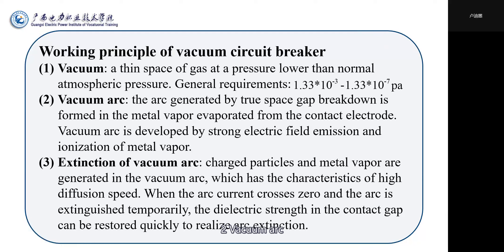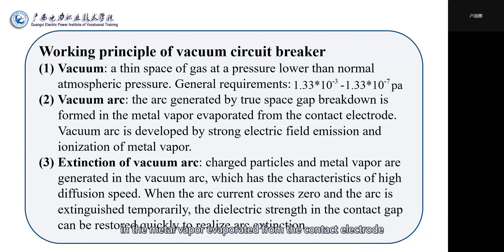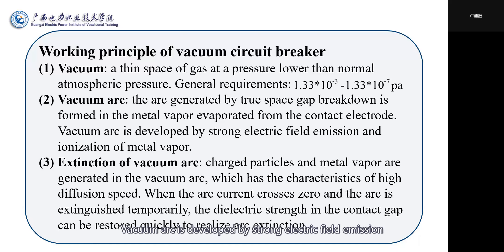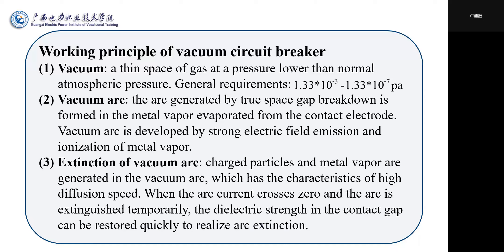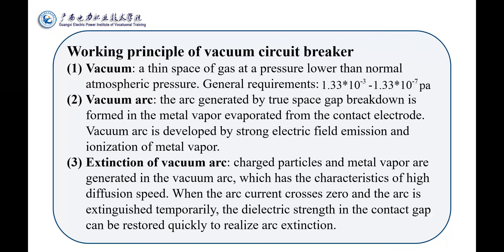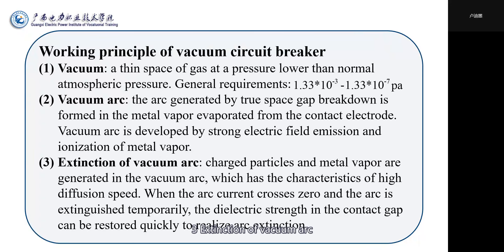(2) Vacuum arc: the arc generated by a vacuum space gap breakdown is formed in the metal vapor evaporated from the contact electrode. Vacuum arc is developed by strong electric field emissions and ionization of metal vapor.